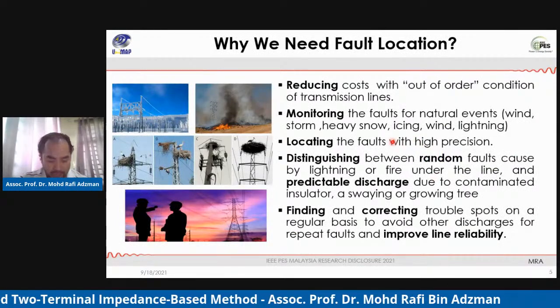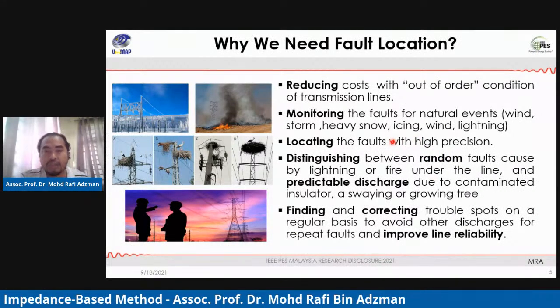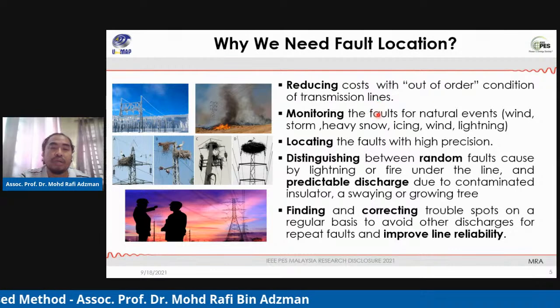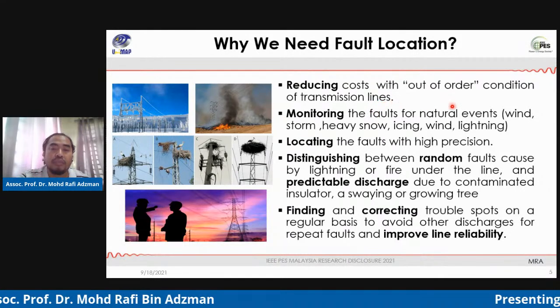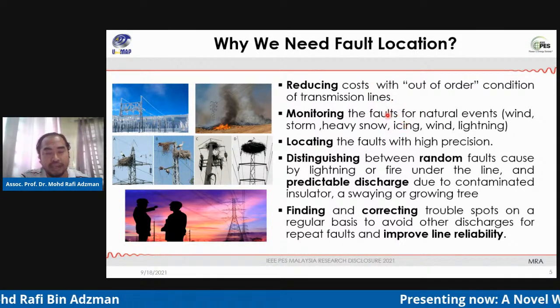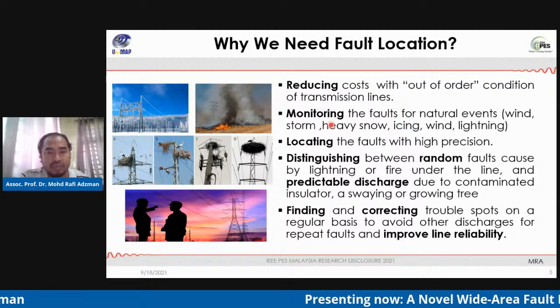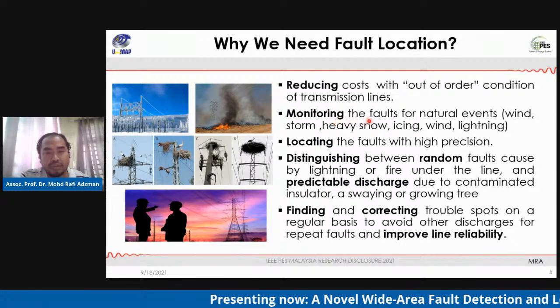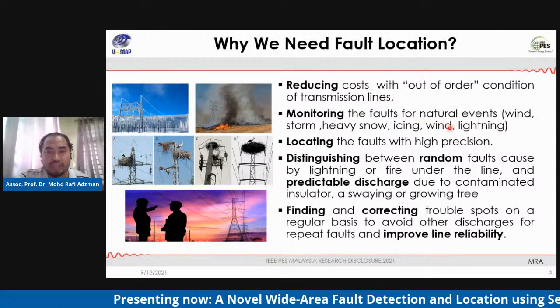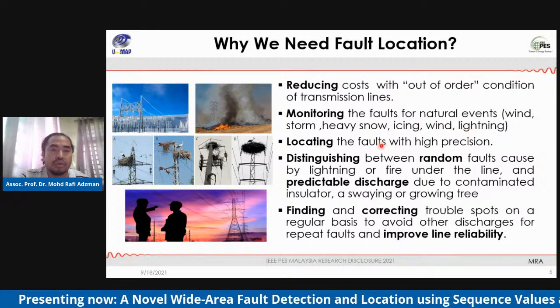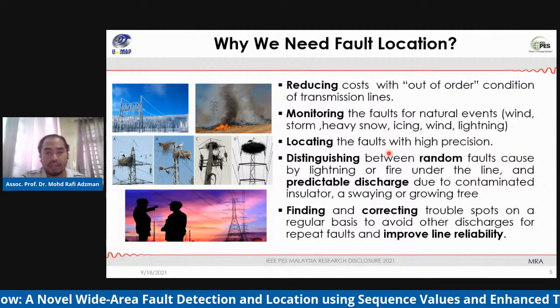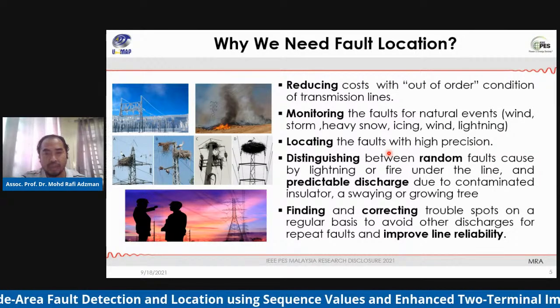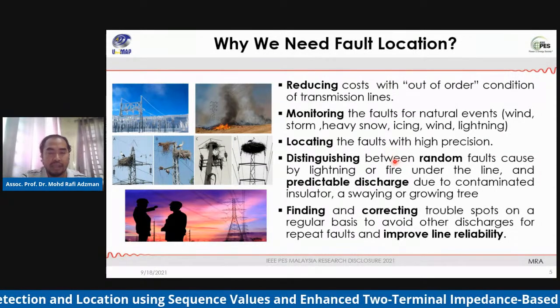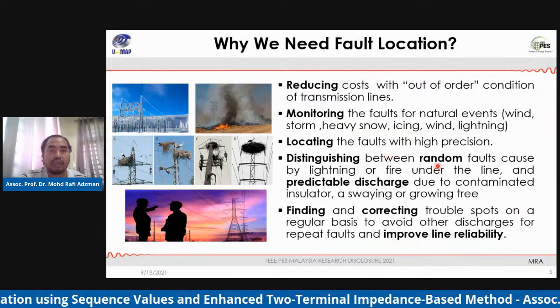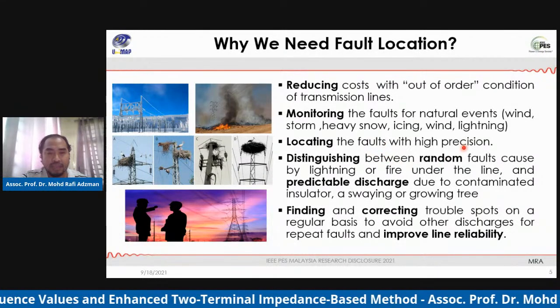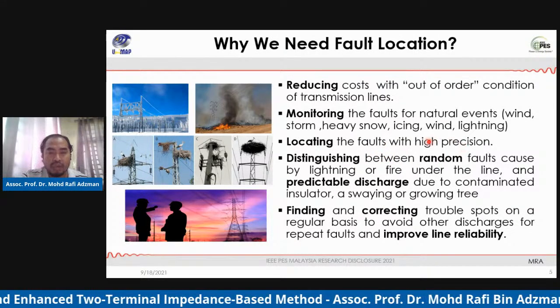So why do we need fault locations? First, we want to reduce the cost of the out-of-order condition of the transmission line. And also we want to monitor the faults caused by natural events such as wind, storm, heavy snow, icing, and also lightning.